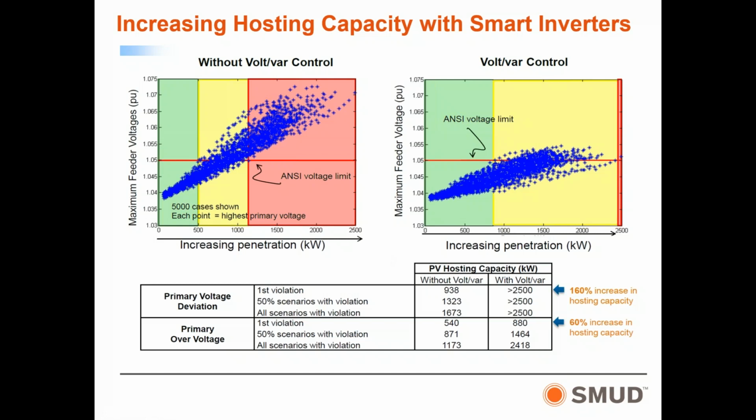Presently, though, probably about 60-70% of our units in the field are pre-smart inverters, so we're trying to phase these in. The investor-owned utilities came up with standard settings that they believe will address most situations. And we are working with the Electric Power Research Institute and NREL, the National Renewable Energy Labs, on a program called PRECISE. This program allows us to take a look at the system, the topography, and create the custom settings that we would need before the customer shows up, so we're not delaying the application process, so we can keep everything moving at a fast track, even when we've reached the first stage of saturation. And with that, I'll ask if we pass it on to go through some questions.